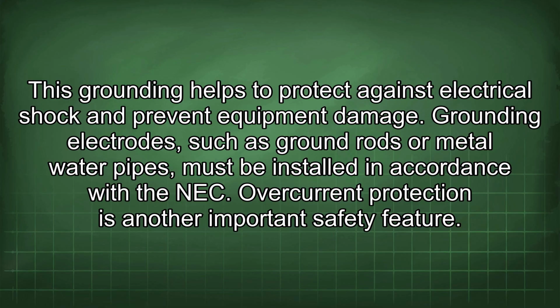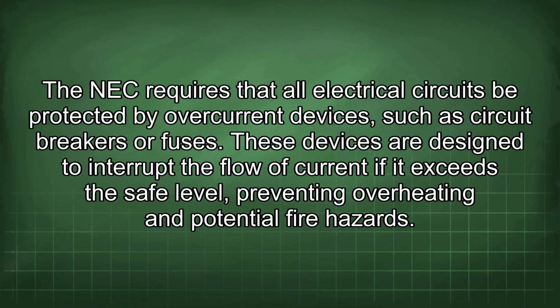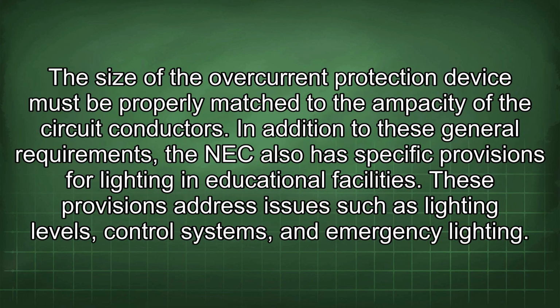Overcurrent protection is another important safety feature. The NEC requires that all electrical circuits be protected by overcurrent devices, such as circuit breakers or fuses. These devices are designed to interrupt the flow of current if it exceeds the safe level, preventing overheating and potential fire hazards. The size of the overcurrent protection device must be properly matched to the ampacity of the circuit conductors.